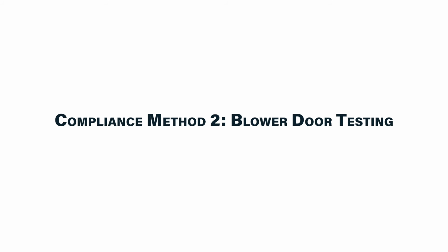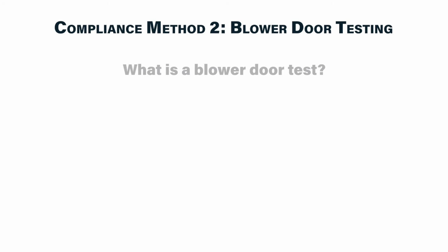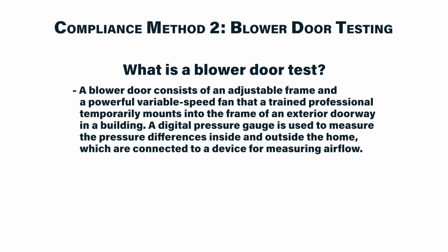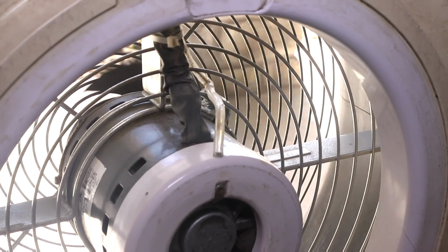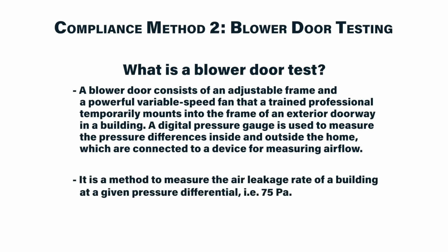The second way to comply with the air leakage section of IECC 2018 is by completing a blower door test. A blower door is a device that pressurizes or depressurizes a building to determine the leakage characteristics of a building's envelope. A variable speed fan is temporarily mounted in a doorway or other opening to pressurize the building by specified amounts. The flow rate through a calibrated orifice is measured at the pressure differential.